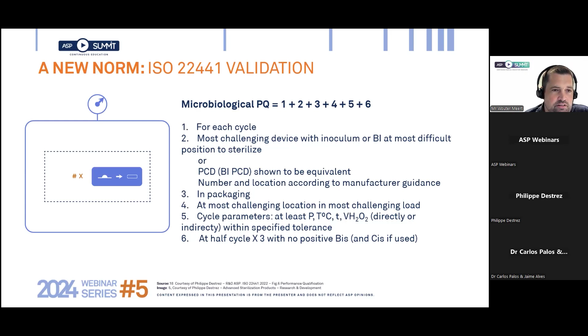Then, looking at releasing loads, is something changing in my releasing loads? I have been using hydrogen peroxide for such a long time, and I released my loads. The machine said my process was fine, and I look at some parameters, but which parameters am I going to look at? In this case, it's sometimes critical versus variable, and that was a difficult thing to do. Critical means that if that parameter is not within the right set points, then the cycle is not okay. Variable parameters are parameters that can vary depending on your load, but if they stay within the set points, your load will be fine.